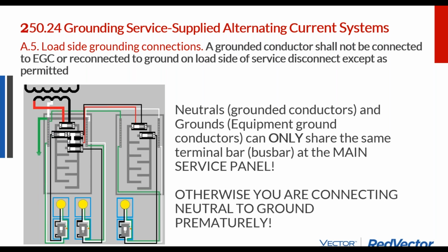For our ground fault detection circuits to work, we need any ground fault to travel all the way through the grounding system, where the ground fault is supposed to go, and out to ground in one spot. And if it doesn't do that, then we can't detect ground faults as easily. So if there's a ground fault, we want that current to be carried back through the system, and to be able to detect that unbalanced current is sensed within the neutral, or at least the difference between what's faulting to ground and what's being returned through the neutral we can measure.